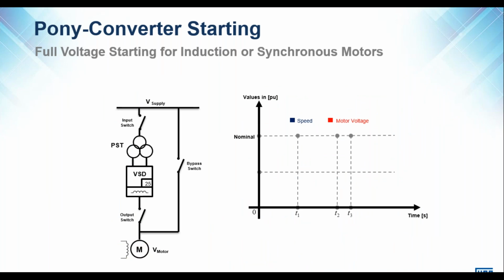Okay, let's get into the details of a start of this nature. All right, so we are able to start the load with the VSD. Remember, we are using a VSD that is smaller in capacity than the size of the motor. So in this case, we start the load and we ramp up the speed, which is shown in blue, and the motor voltage is ramped up linearly in proportion to the speed.